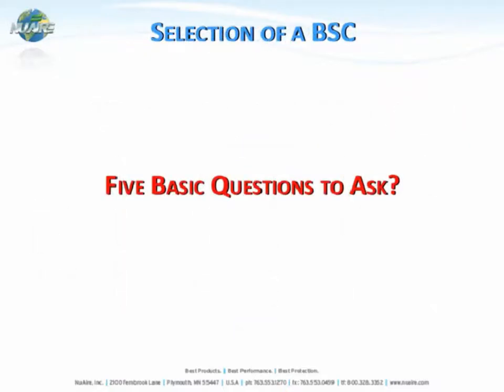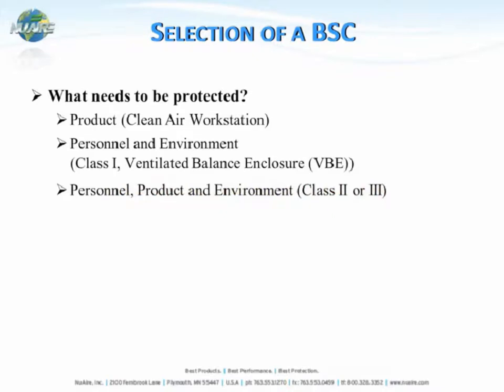Once you consider those items, you'll come up with five basic questions to ask yourself when looking to purchase a biological safety cabinet. The first question is: what needs to be protected? Is it just the product, which is accomplished by using a clean air workstation or horizontal laminar flow clean bench — providing HEPA-filtered air over the work surface for product protection, but not personnel protection since the airflow blows right at the user? Or do you need personnel and environmental protection only, like a Class I, if you're working with toxic powders that don't require product protection?